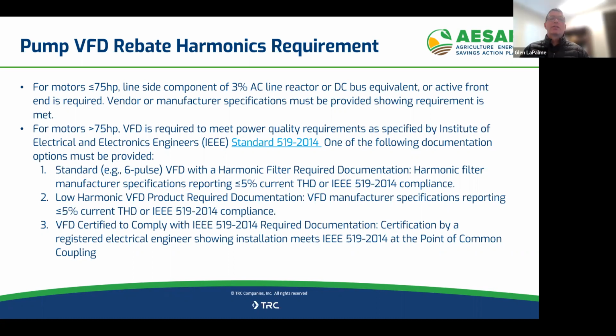And I can respond to Neil's question. On that third option, I agree with the point about being able to get access to that point of common coupling. We don't anticipate that anyone's going to pursue that path, although it is a viable option per code under the IEEE standard. But it's costly and difficult to get all the information. We kept it in there for completeness, but our expectation is that if people are going to comply, they'll take a standard 6-pulse VFD and add a harmonic filter to it. That would be the most common way to comply with this requirement, or buy the low harmonic VFD product, which would probably cost a bit more but would still comply.